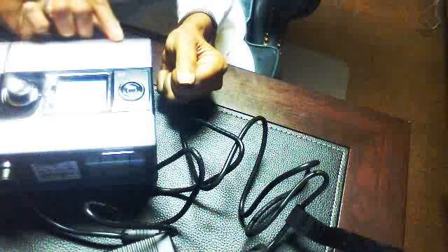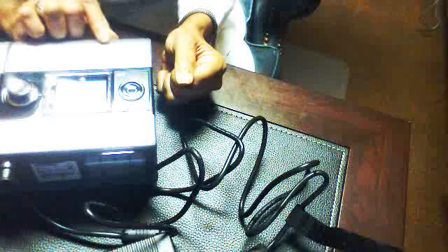So this ramp is currently set at 15 minutes. Let's just use an example of a person who has CPAP set at 8 centimeters of water pressure. When the machine is turned on, it will start at a very low pressure. Right now it's running at 4 centimeters of water pressure. And gradually between now and the next 15 minutes, the machine will ramp up the pressure so that it will be delivering 8 centimeters of water pressure at 15 minutes. The thinking behind this is that you'll be asleep in 15 minutes, so the air pressure will not disturb your sleep. It will actually help you sleep by maintaining the patency of your airway.